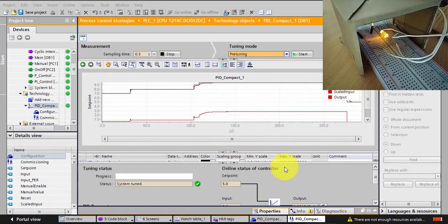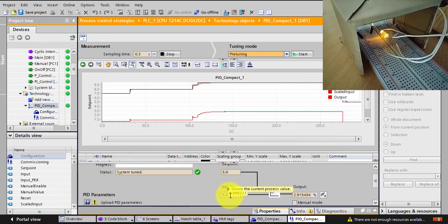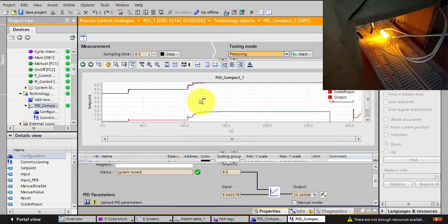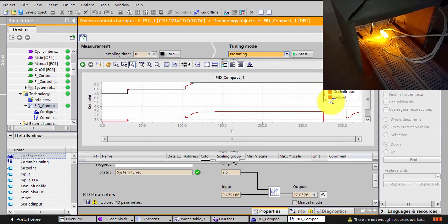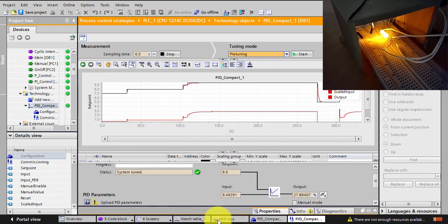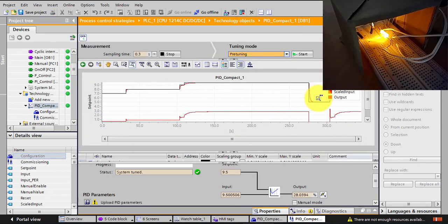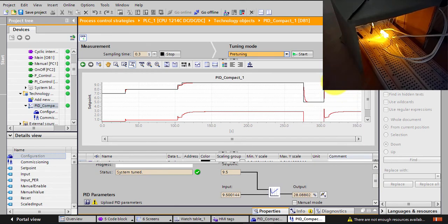My setpoint is at 5 and my PV is 4.9 — wonderful. Now I'll change the setpoint to 9.5. Right away the LED brightness changes and the input is going up slowly. You can see the change from 5 volts going up to 9.5. The tuned values the PLC came up with were a proportional gain of 10 and an integral action time of 1.2, giving a smooth response. Removing the legend, you can see how the system is responding to the setpoint.